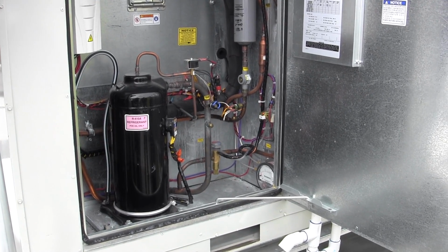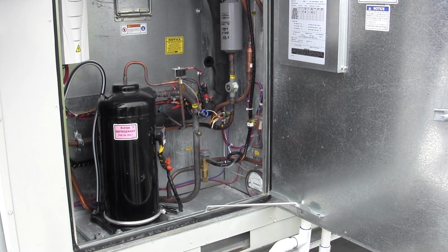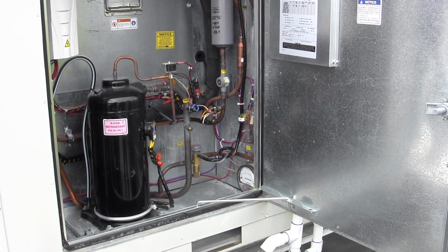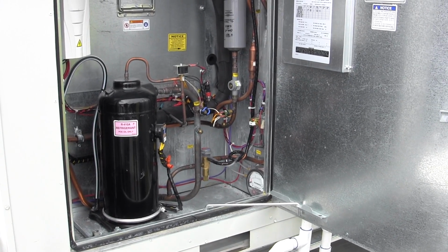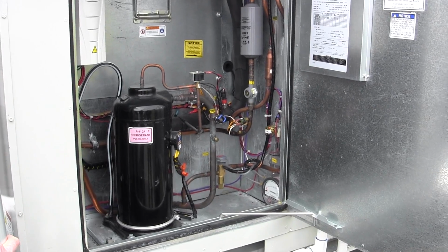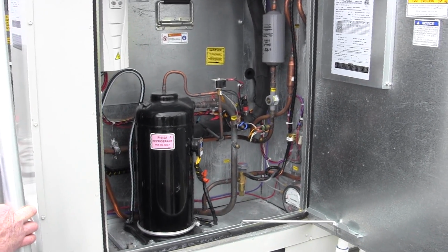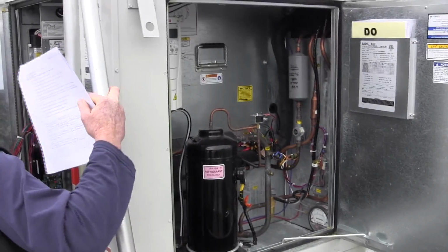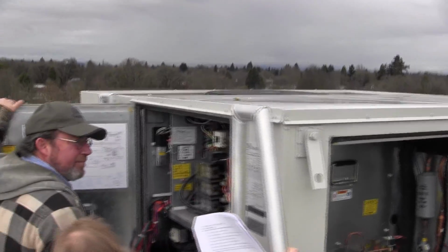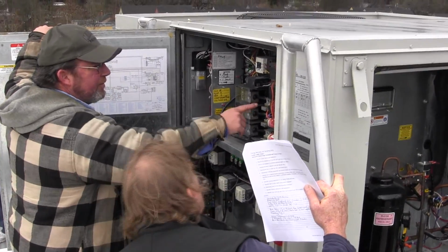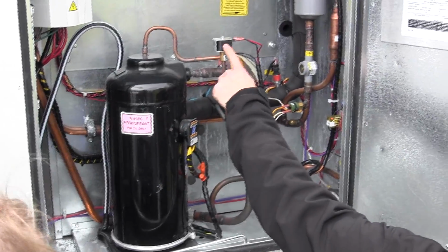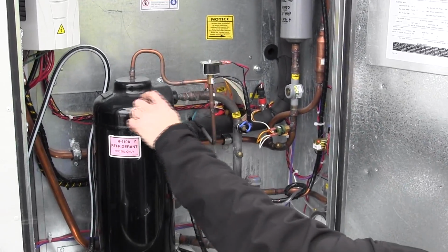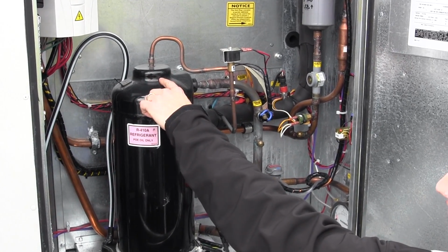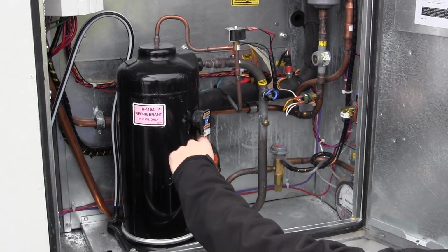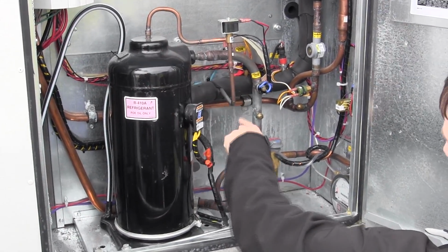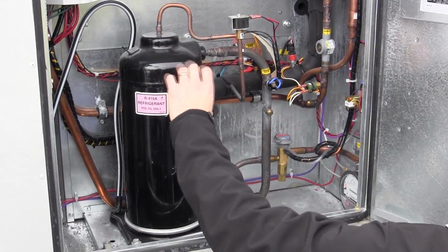Okay, this is something. It's wrapped. 410A, are they all using 410A? Yes, it's all 410A now. Well, yeah, just like the old town. And these little toggle switches is what designates the digital scroll. So this solenoid, when it opens up, it relieves a little bit of pressure on this diaphragm right here, and that's what allows the thing to go up and down. Yeah. Right there, right? So it's not actually hot gas. Some people think it's hot gas bypass, but really all it is, is relieving the pressure just enough so that it opens and closes.